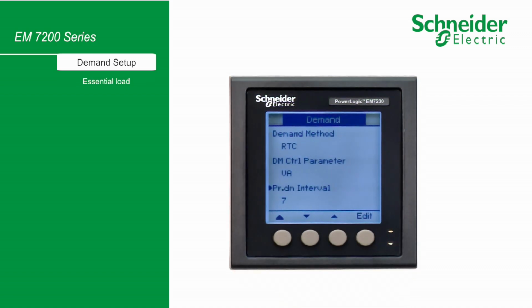This innovative feature enables you to exclude some of the essential loads from the demand controlling option. That means demand is calculated for the entire connected load in the system, but the computation for the controlling technique does not include the essential load factor. If you are unsure about the essential load factor, we recommend you set the value to 0 or near 0.